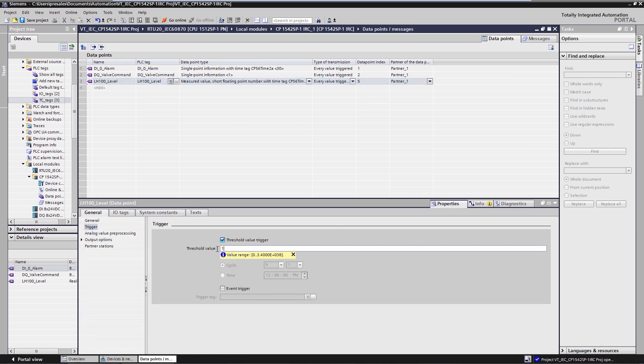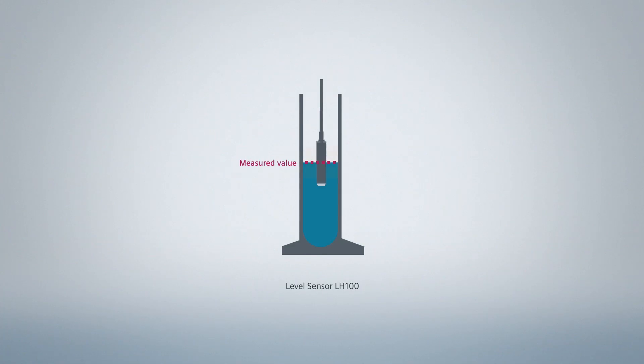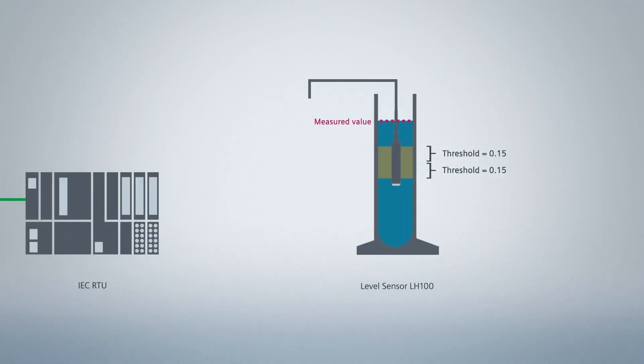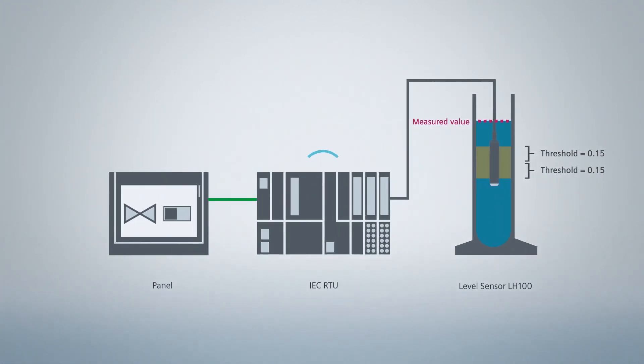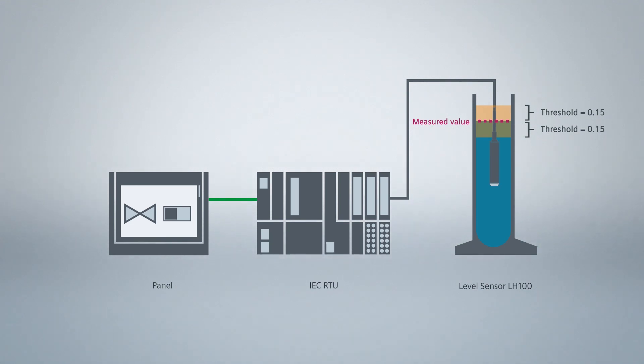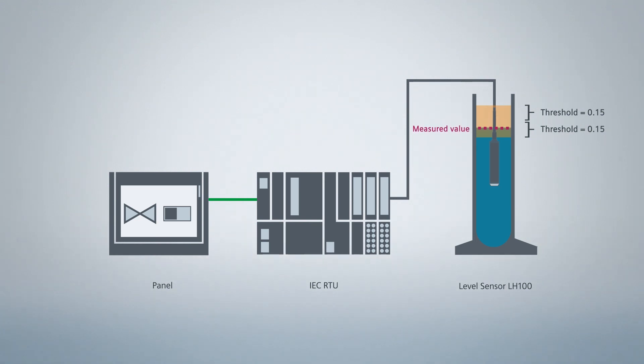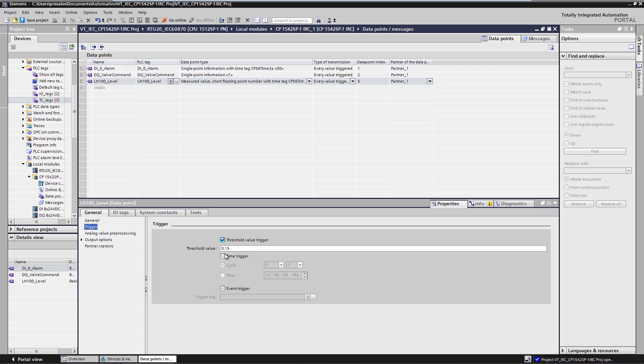For the measured value, we still need to define the appropriate threshold value. Only if the measured value experiences a change greater than the threshold value will it be transmitted to the control center. This ensures that not every small change triggers a transmission and thus prevents unnecessary traffic on the communication route. We could of course also choose other criteria, such as cyclic data transmission or combined transmission criteria.